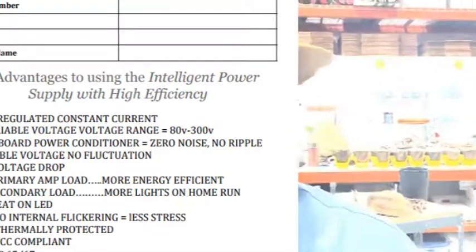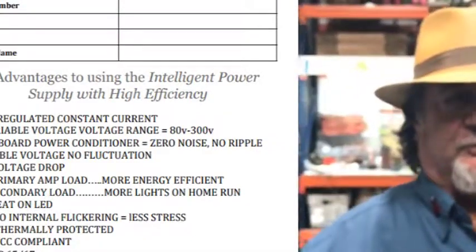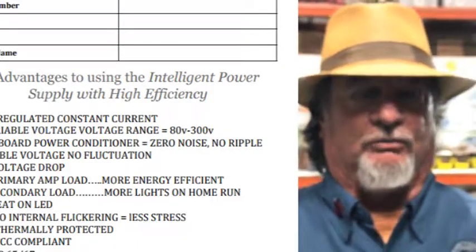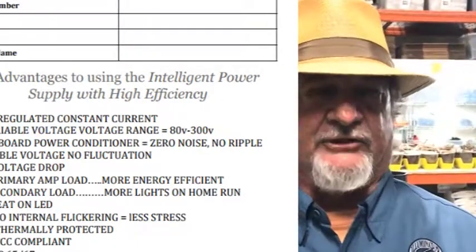There is zero humming noise. How many times have we been on a job and put a transformer on a bedroom wall? We've got complaints from the homeowners that it buzzes and vibrates. Zero vibration, zero buzzing. Yes, smart sensing technologies, which I went over about when you overload it. So those are the things that I can think of. I'm pretty sure there's going to be probably one or two more.